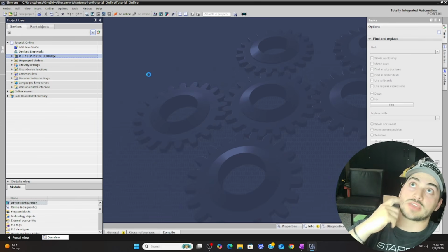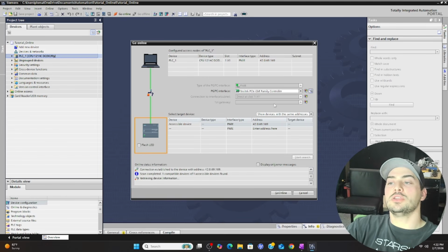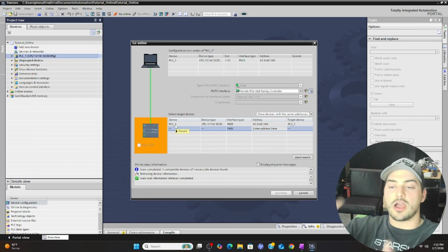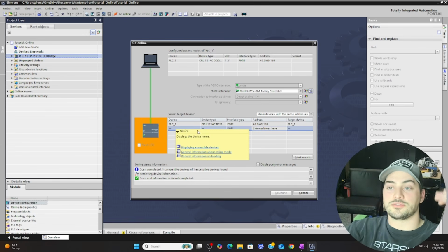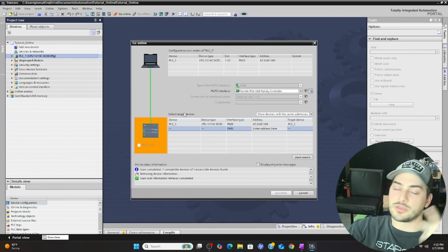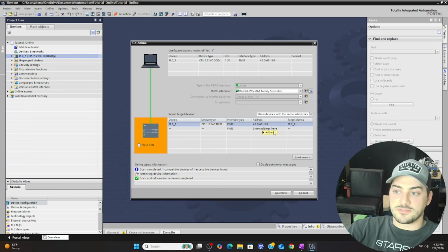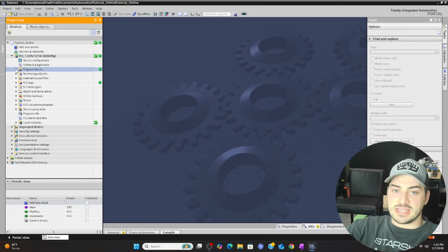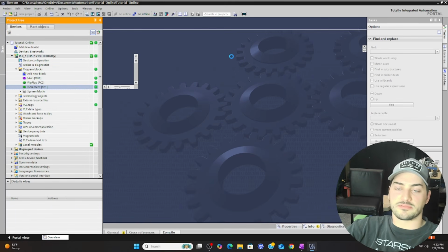If I didn't have the Go online button, you can usually use Extended go online, or older versions of Allen Bradley PLCs had Who Active Go Online, where you can check for available IP addresses and devices, and you can see all the devices available to you that you're connected to through a variety of drivers, whether it's serial, Ethernet, Profinet, whatever. And then you can check for your device, see if it's connected, and then go online that way as well. Okay, and we can once again see that we're online. We can get back into the Increment code and we can live monitor it.